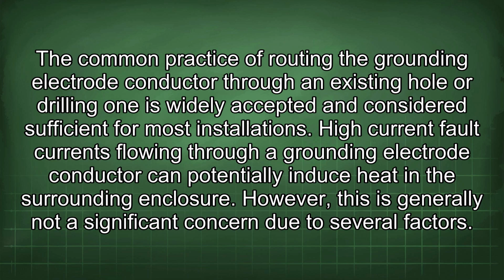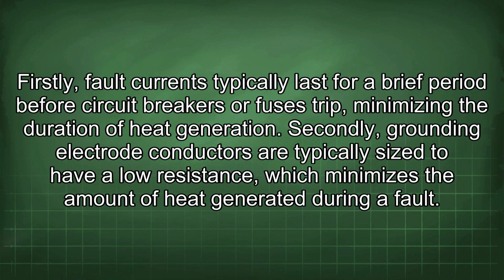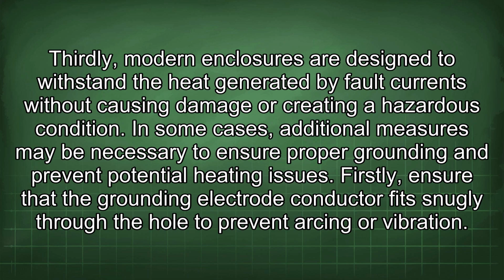High fault currents flowing through a grounding electrode conductor can potentially induce heat in the surrounding enclosure. However, this is generally not a significant concern due to several factors. Firstly, fault currents typically last for a brief period before circuit breakers or fuses trip, minimizing the duration of heat generation. Secondly, grounding electrode conductors are typically sized to have a low resistance, which minimizes the amount of heat generated during a fault. Thirdly, modern enclosures are designed to withstand the heat generated by fault currents without causing damage or creating a hazardous condition.